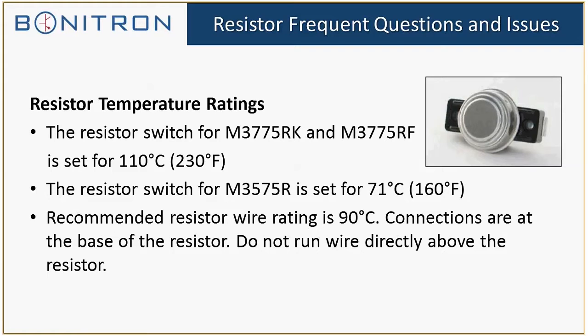As for the actual wiring going out to the resistor, we recommend 90 degrees centigrade wiring. Even though the resistor can get much hotter than that, the wires do enter the resistor from the bottom, and we definitely do not recommend running the wire directly above the resistor, as well as they should give the resistor plenty of space around it, up to 2 to 4 inches depending on the size. But yeah, 90 degree rated wire is absolutely fine for basically the operation and running out to the resistor.